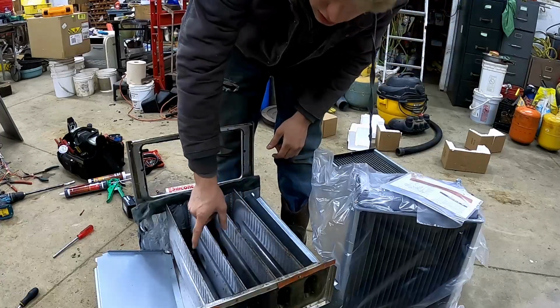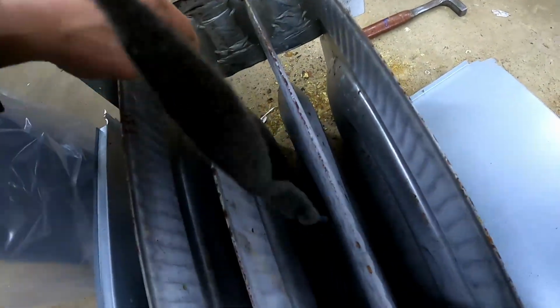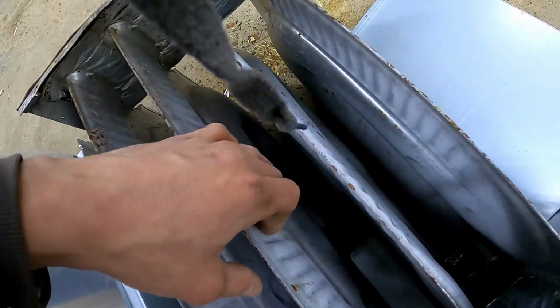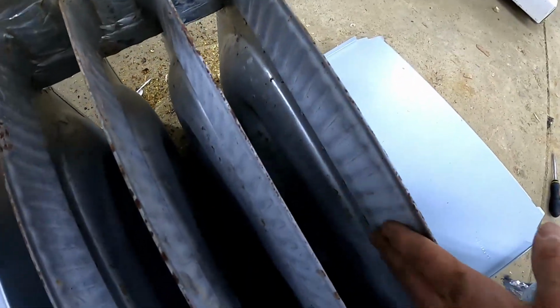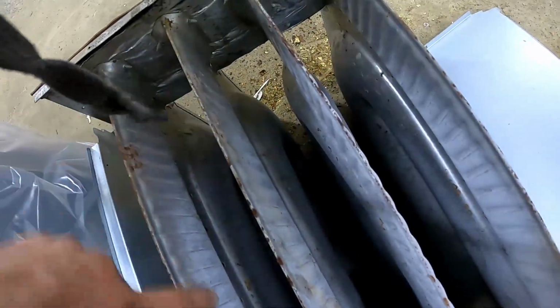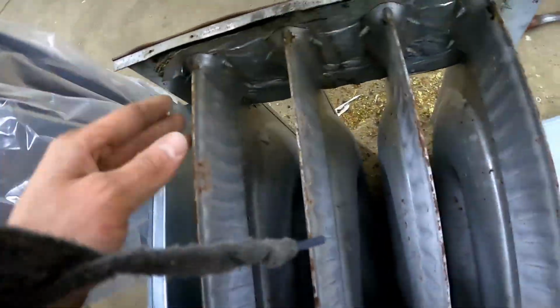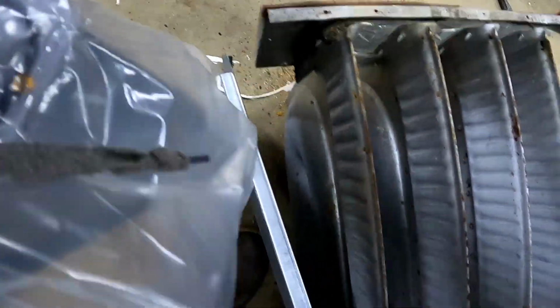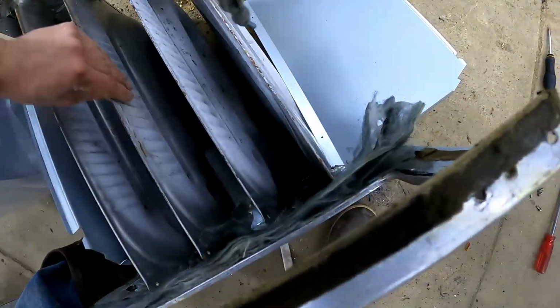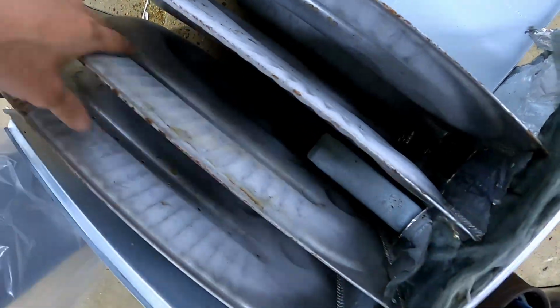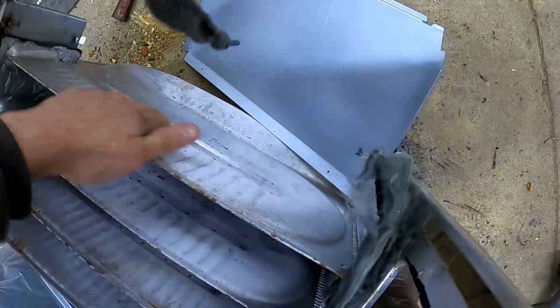At this point, you want to inspect your primary heat exchangers. It's not uncommon for them to rust through and have pitted spots, so you just want to go through and inspect each one. This one has some surface rust, but you can see none of that goes deep and actually pits through. So it does not look like any of these will need to be replaced.